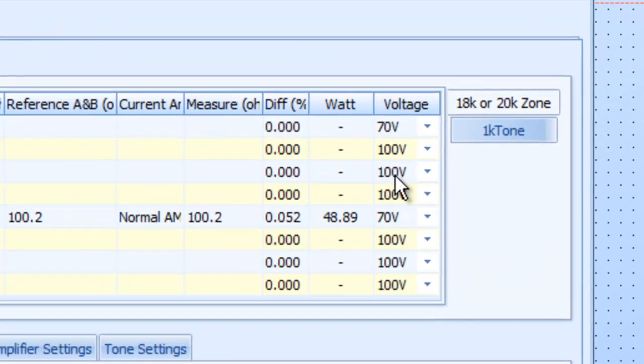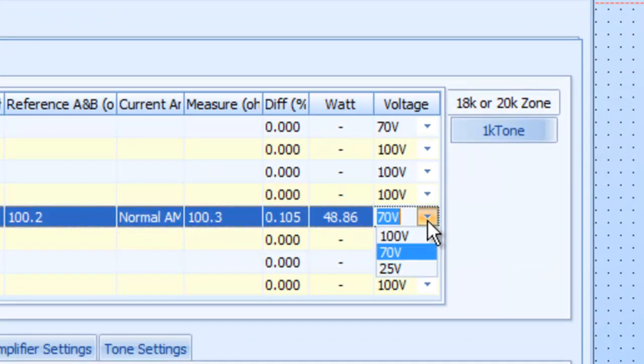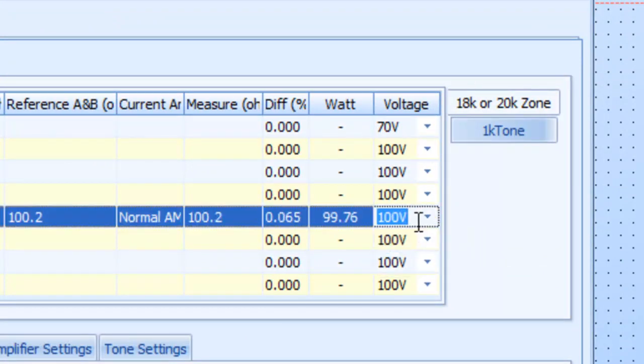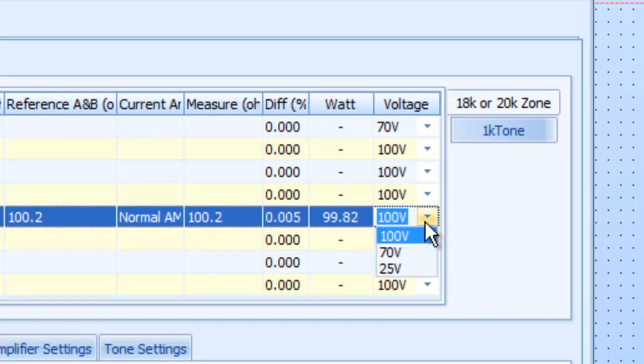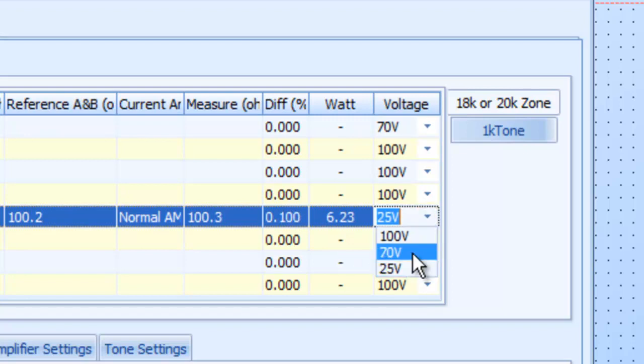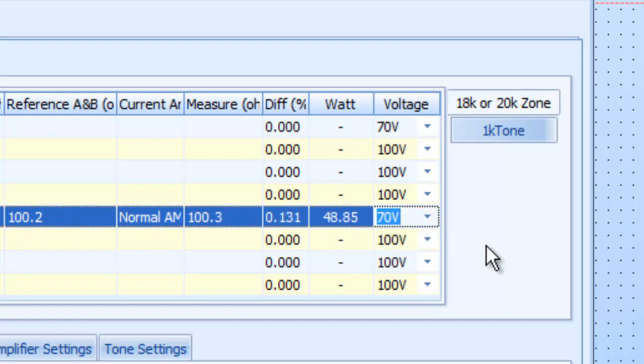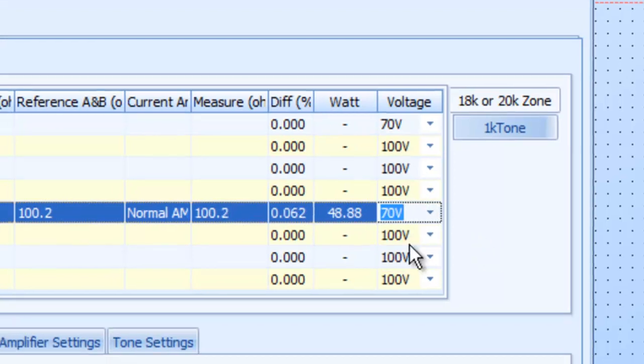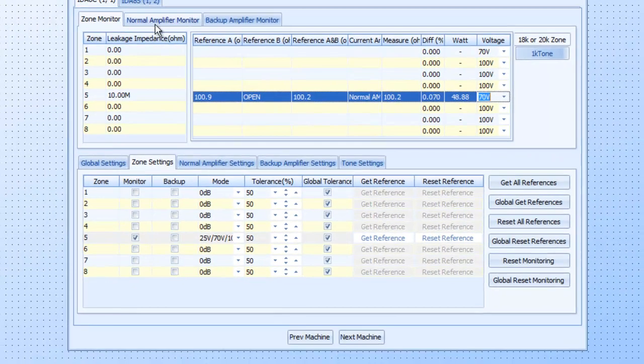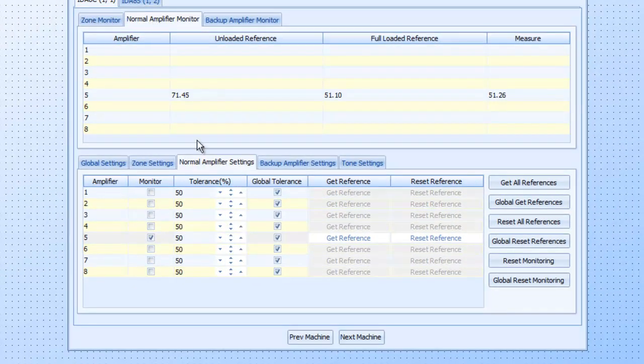Also on your circuits up here, this is where you set it for the voltage. And you can do this while you're actually online. You can see the measurement when we got the reference. It thinks it's a lot higher at 100 volts and a lot lower at 25 volts. But we're actually hooked up at 70 volts. And that's right. So also make sure that these are correct as well.